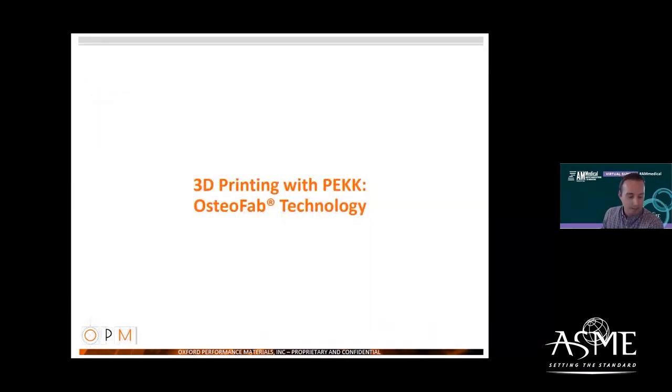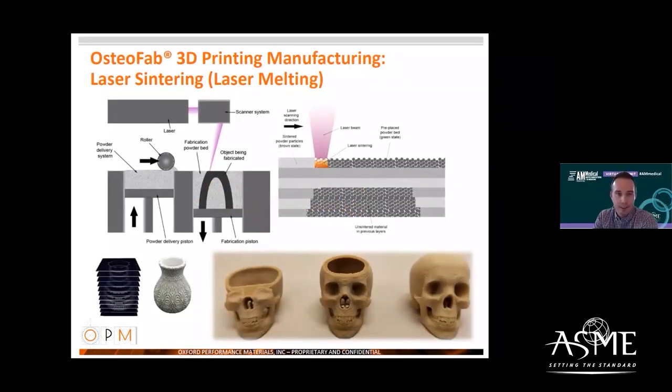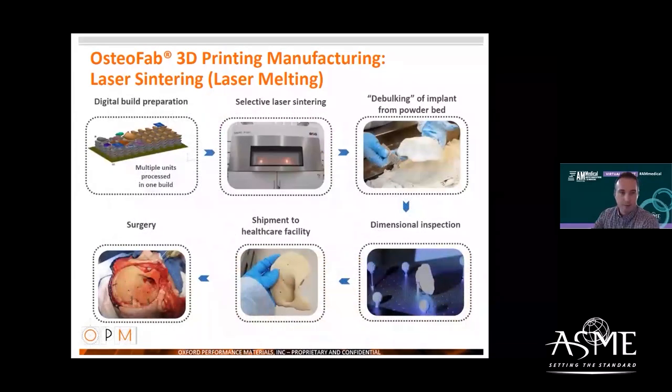The OsteoFab technology is our term for the laser sintering or laser melting of PEKK powder. We take a CAD model, divide it into sub-millimeter 2D cross-sections, and create a part by successively melting layers of powder in the print bed until the part is built up in three-dimensional space. Unlike metal-based processes, no supports are needed. Parts are excavated from the powder bed, inspected, and shipped. They are autoclavable at the healthcare facility if needed.